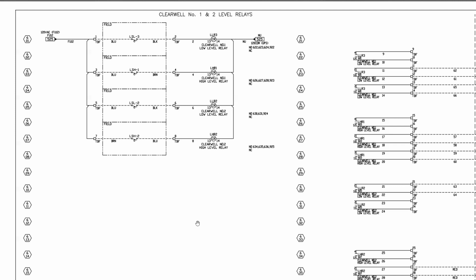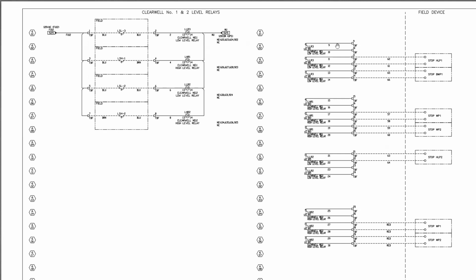What you'll see in the field is electricians will pull a bundle of wires from point A to point B, and they'll label them, and they'll have like a pack of just 1 through 9, a whole like thousands of stickers, and they will just label all of those cables that they're pulling. And if they're not told what to put on them after the fact, so if there were no drawings that said, hey, this is actually going to be 601, 602, 603, they're just going to leave them as 2, 3, 4, 5, 8 because that's the labels that they put on when they pulled them in. So in this case, yeah, you're right. These don't make any sense. And it's highly possible that you would end up duplicating when you label them like this.